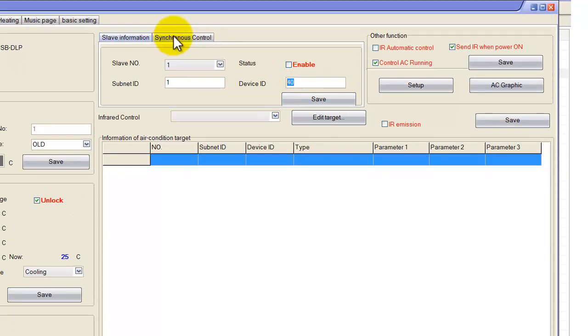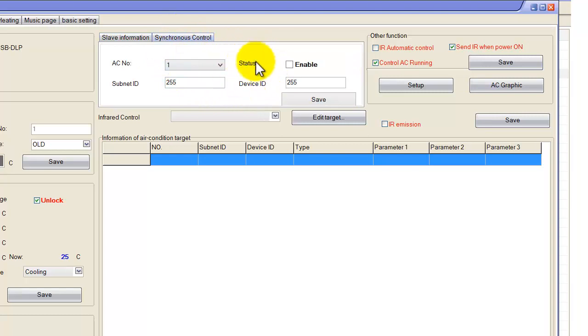We have 'Synchronous Control'. We use this to synchronize temperatures between two DLPs in the same room that are controlling the same machine, so it gives you the average temperature. Because if two DLPs are placed far apart in the same room, there could be a 2 to 3 degree difference due to supply and return airflow. The DLP has the option to synchronize between two DLPs and give you the average temperature, so all DLPs work on the average.